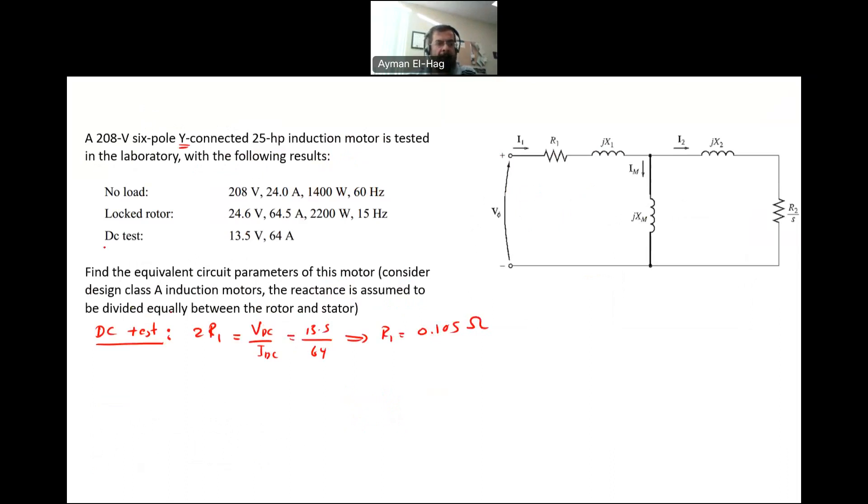Now we will use the no-load test. In the no-load test, we apply the rated voltage, the rated voltage line-to-line which is 208 as mentioned in the question. We will have the no-load current, which is basically the magnetization current. I2 will be almost equal to 0, so the whole current goes through R1, X1, and XM in series.